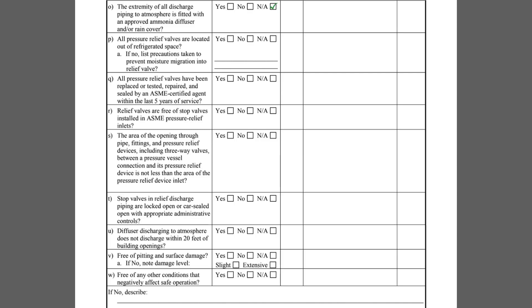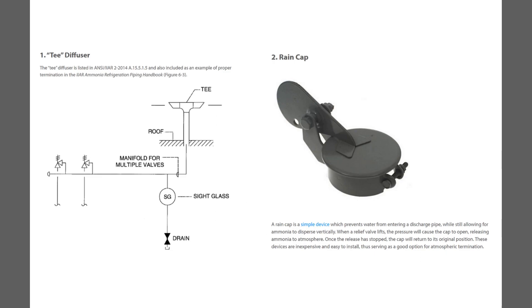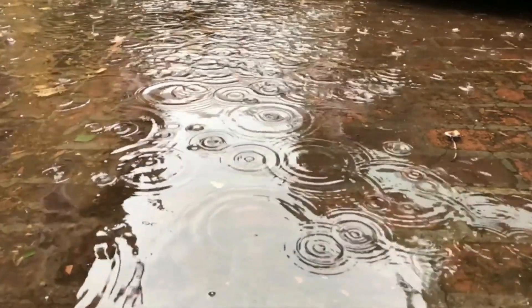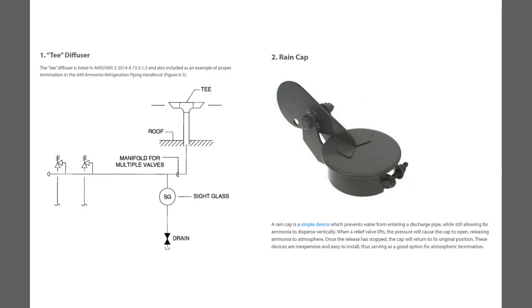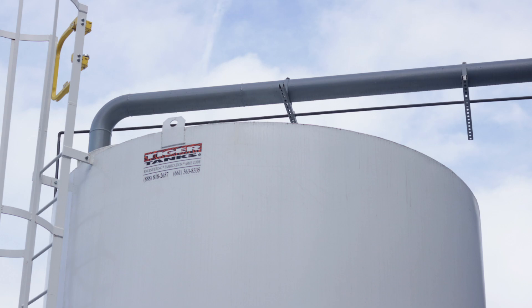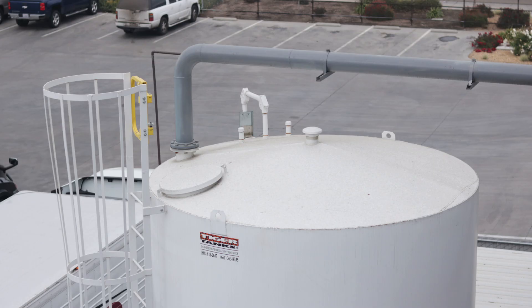Item O asks if the extremity of the relief valve termination pipe to the atmosphere is fitted with an approved ammonia diffuser and/or rain cover. If a relief system terminates to the atmosphere, the termination point may be susceptible to rain or snow, therefore means to prevent rain or snow from entering the pipe is required. IIAR Standard 2 states that permissible covers include a double 45 degree diffuser, a bull's horn diffuser, a self-closing flapper cap, a sock hood cover, or exterior stack extension diffuser. This relief system terminates into an ammonia diffusion tank, so the question is not applicable.